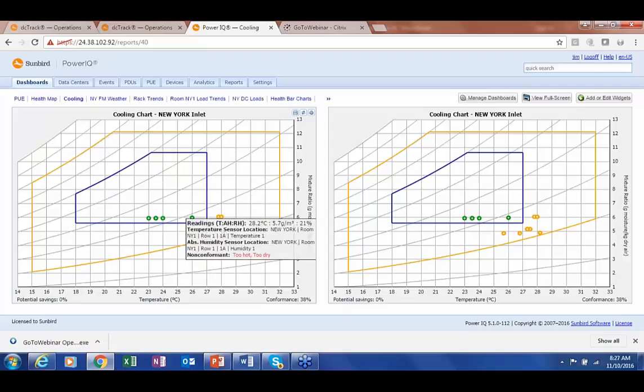Cabinets that are outside of that range, but still within the ASHRAE allowable range to let you leverage new techniques like free cooling, are highlighted in yellow with an additional non-conformance explanation, such as too hot and too dry for sensors in this area. Sensors in this area are just too hot. If the sensor was over here, it would be too damp and might create corrosion. And over here is too cold, where you're just wasting energy.